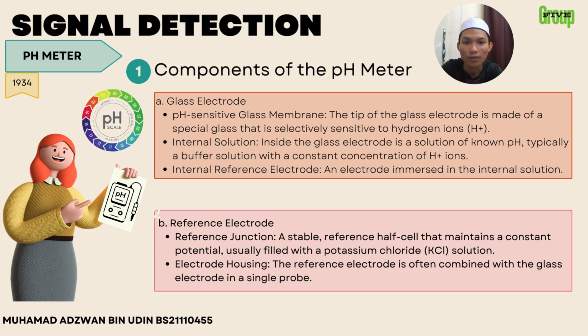Internal solution: inside the glass electrode is a solution, typically a buffer solution with a constant concentration of H+ ion. Next is the internal reference electrode, an electrode, often silver or silver chloride, immersed in the internal solution. For the reference electrode, we use a reference junction, a stable reference half cell that maintains a constant potential, usually filled with a potassium chloride solution. Next is the electrode housing. The reference electrode is often combined with the glass electrode in a single probe, but it can also be a separate electrode.